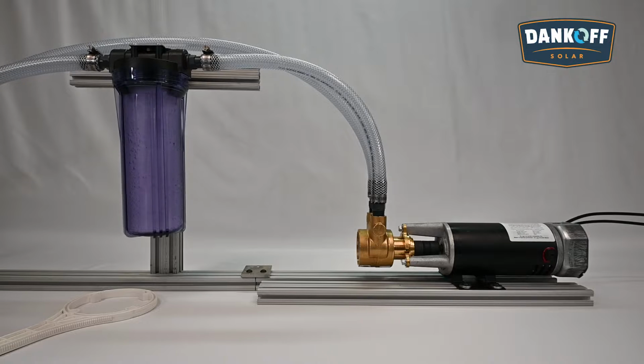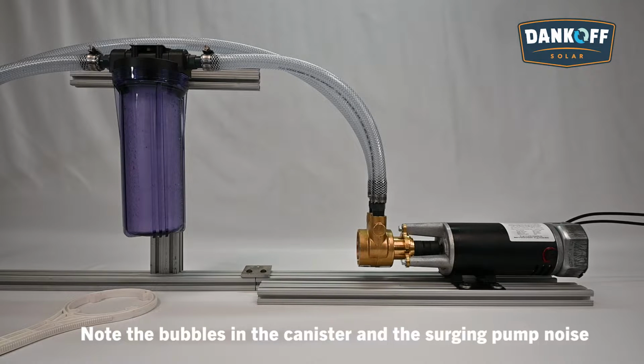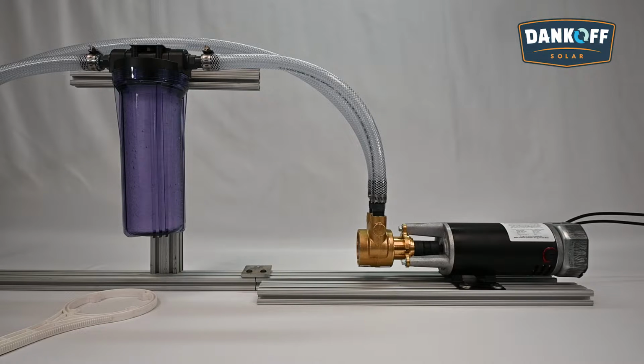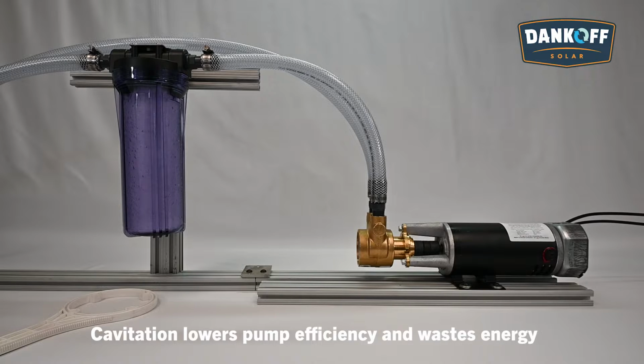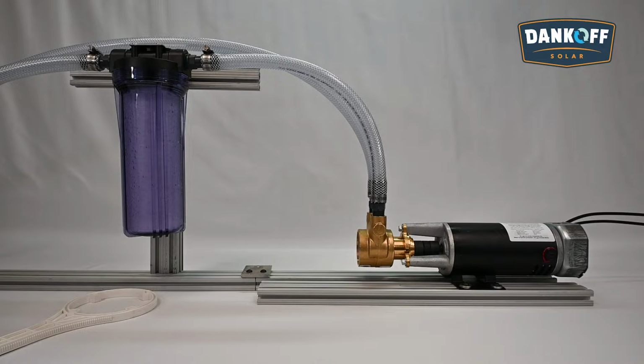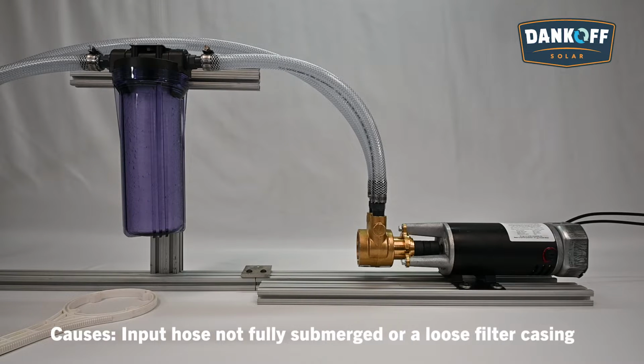A pump that is laboring and surging, or a filter housing that is having air introduced into it, is most likely cavitating, shown here. Cavitation dramatically increases the load the pump sees under otherwise normal conditions, which lowers the efficiency and wastes energy. The most common cause of cavitation is either an input hose that is not completely submerged or a loose filter housing casing.